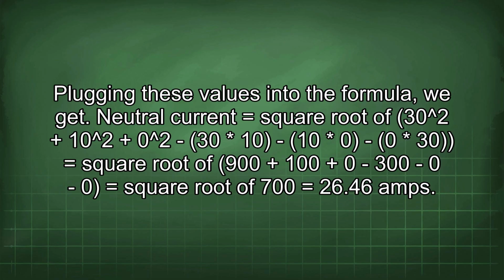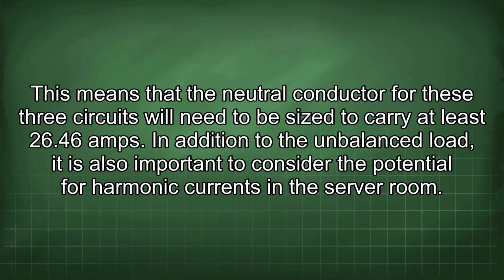Plugging these values into the formula, we get neutral current equals the square root of 30² + 10² + 0² − 30*10 − 10*0 − 0*30, which equals the square root of 900 + 100 + 0 − 300 − 0 − 0, which equals the square root of 700, or 26.46 amps. This means that the neutral conductor for these three circuits will need to be sized to carry at least 26.46 amps.